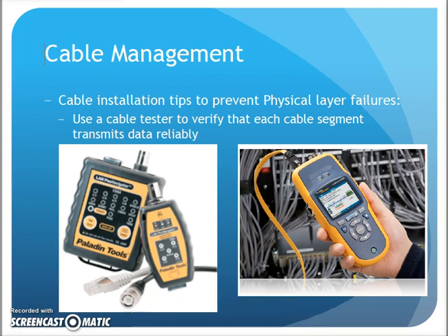After installing my cabling, I should put a cable meter on it and test for continuity, and maybe even do additional testing for wire maps and distances and that sort of thing. This eliminates, or tries to cut down, the number of future failures that you might have in your cable system.